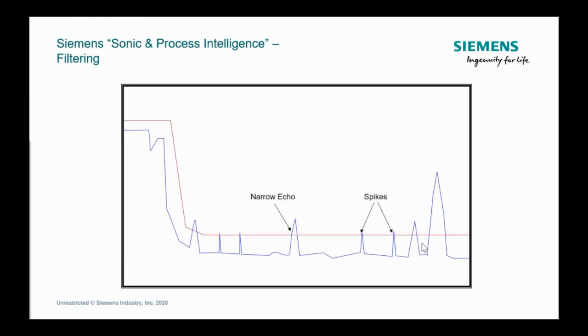We were talking about a spike and a narrow echo filter. I've seen spikes from anything from bolts of lightning to big motor starters kicking on, where you get kind of a flyback effect or an electrical spike, if you will. The spike filter is exactly that. In the old Hydroranger speak, that's parameter 821. In the new Hydroranger HMI, it's called spike filter. Okay. You have the option of turning it off or on. By factory default, it is on to take out those really short transient spikes out of the echo.